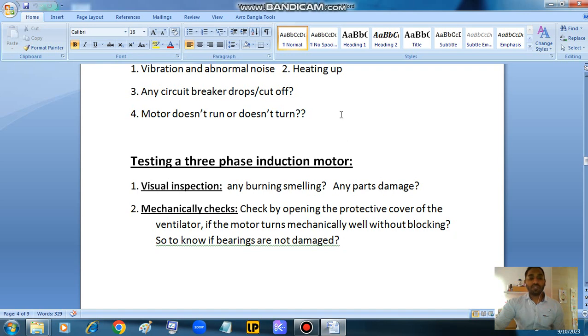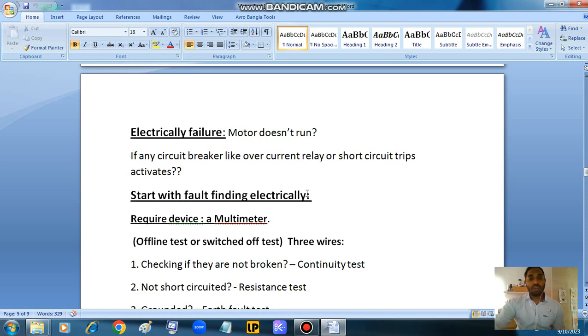The first and foremost test is visual inspection. We have to check visually, maybe a burning smell comes out, or some parts are damaged. Then mechanical checks: we have to switch off the power to the motor, open the protective cover of the ventilator, and turn the ventilator to check if it blocks or turns without any problem. If it blocks, maybe the bearings are damaged. Electrical failure means we try to switch on the motor with the push button, but the motor doesn't run, or it runs but after a few minutes or hours the overcurrent relay or short circuit breaker trips.